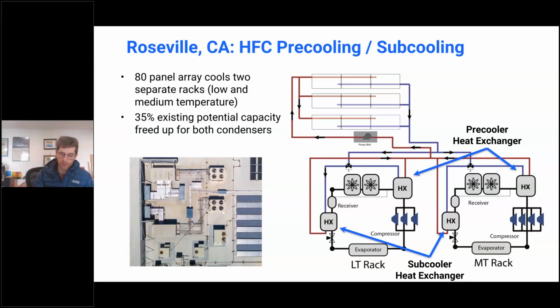And then in the cooler times, the condenser has enough capacity. We would subcool refrigerant, adding efficiency to the system, and they can continue to operate until they do their CO2 conversion. And then at that point, essentially, they would replace the heat exchangers with high pressure versions of the same heat exchanger, and it would still continue to provide efficiency value to the store for the next 10 years or so. The entire lifetime of the panels is 10 to 15 years. But yeah, the first couple of years would be as this booster to the existing equipment.